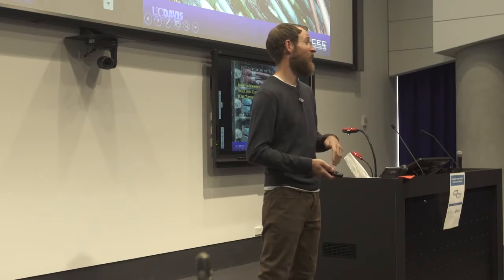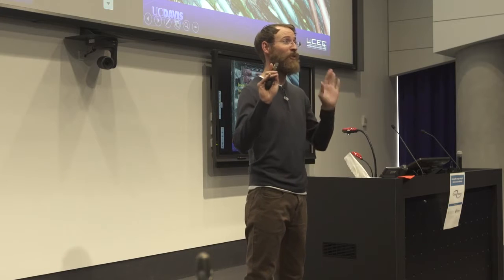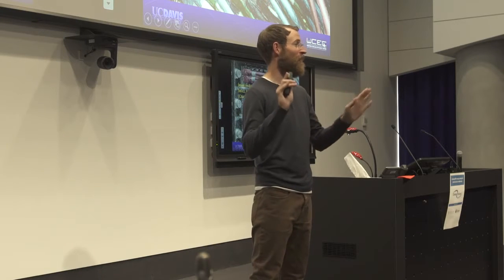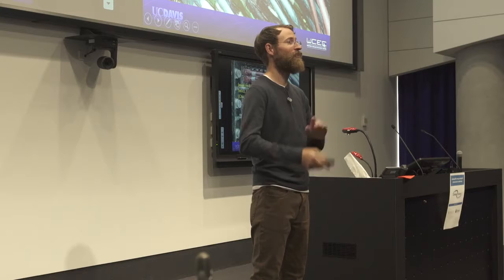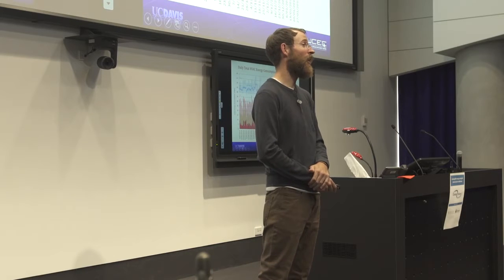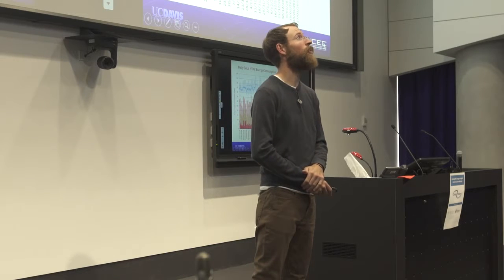Currently the way that they do it is with two wall-mounted air conditioners that are designed as a kind of N+1 redundancy to make sure that if one fails, they always have a backup. But it turns out, actually, the way they run it is as a first stage and second stage. They're running oftentimes both of those compressor systems at the same time to try to keep that space cool. So they use a lot of energy just trying to keep their electronics cool.